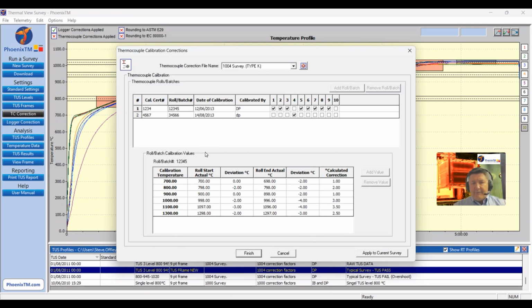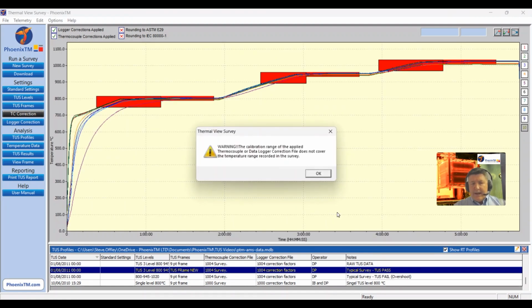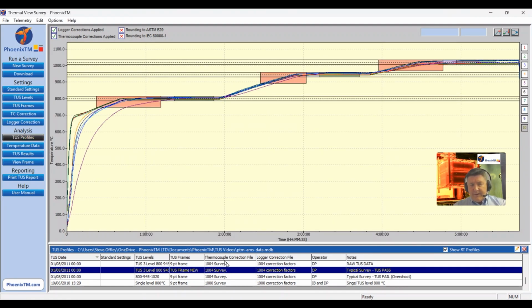So for the two batches, I have two separate calibration tables set up. For 1, 2, 3, 4, I've got a calibration table ranging from 700 to 1300 degrees with the roll start, end values and the corrected correction factors. And for the single thermocouple on its own, thermocouple number 4, a different calibration, but again over a similar temperature range that covers the TUS that we're actually performing. To apply this, as is convention, I simply press apply to current survey, and you'll notice now that the survey file, the correction factor file, is now live on the database, and the status is updated in the top left-hand corner of the software screen to indicate that both data logger and thermocouple correction factor files are applied to the TUS data that we're now looking at.